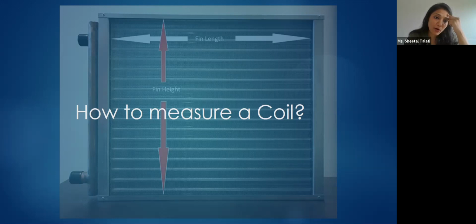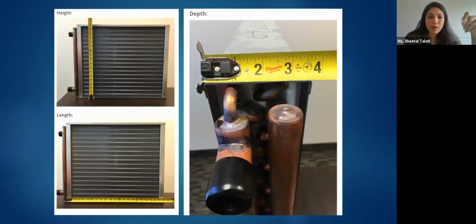But when the coil is an odd coil, the measurement of the coil is very, very important. You have to measure the coil correctly. Otherwise, there are a lot of problems on site. You are not able to fit the coil. The coil is undersized or oversized. So how do you measure a coil? You measure the fin height and the fin length first. Then you measure the coil from end plate to end plate: end plate to end plate height, end plate to end plate length. Later, you take the depth into consideration. You measure the depth of the coil as shown in the diagram. You give the dimensions in millimeters or inches. Millimeter is preferred because it is more precise.